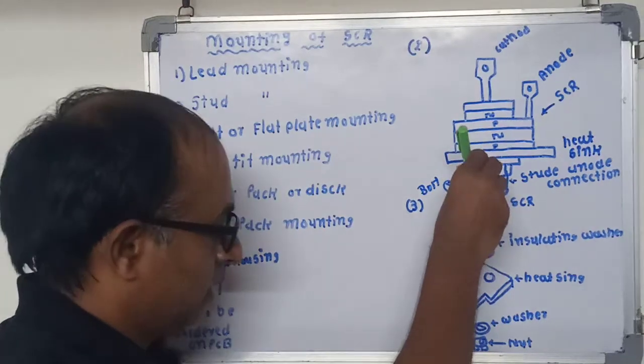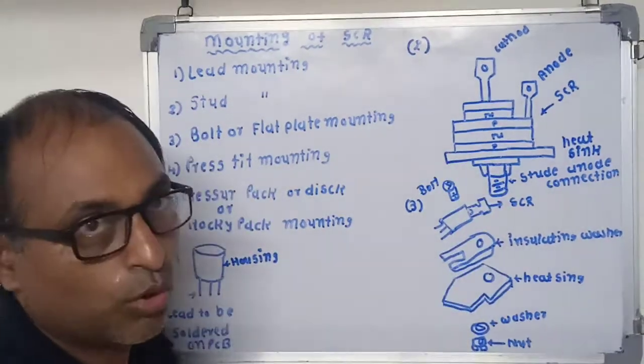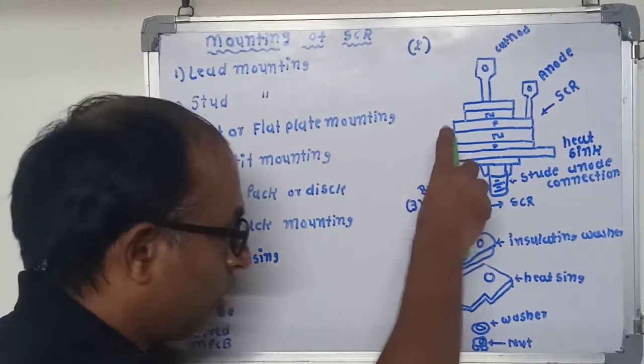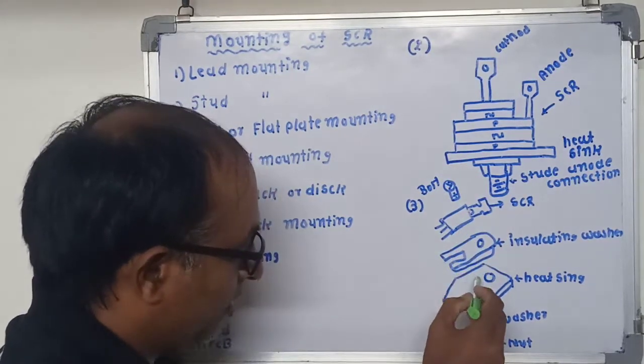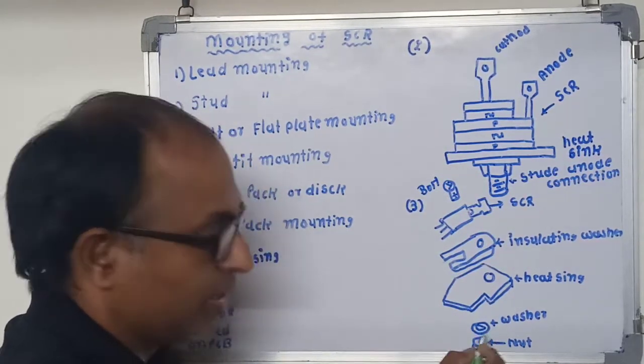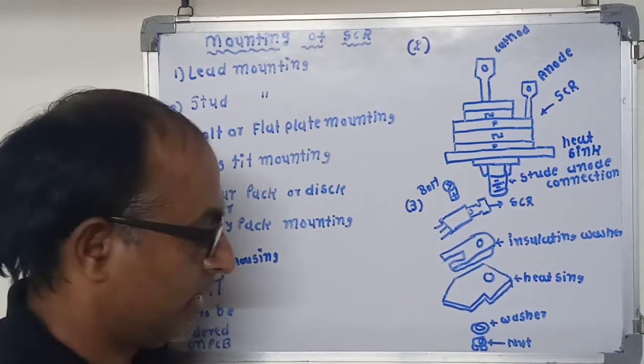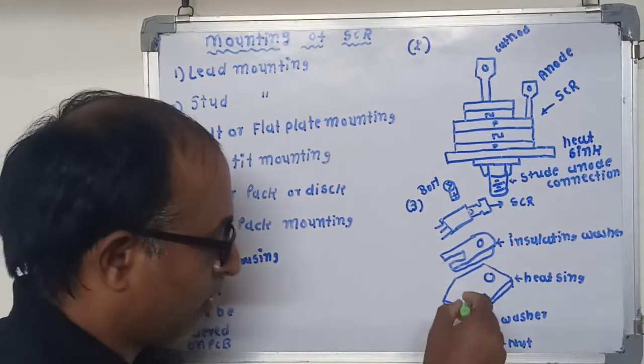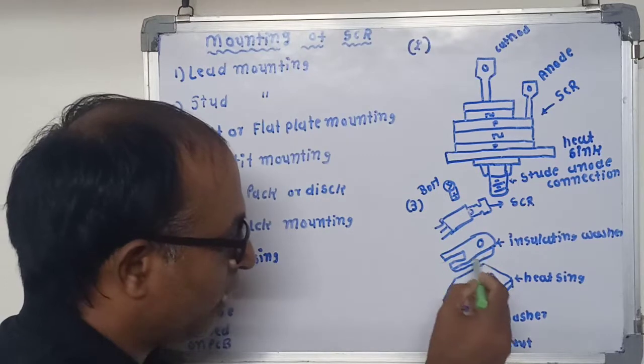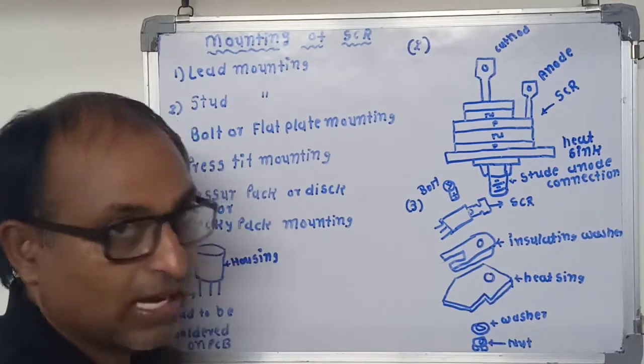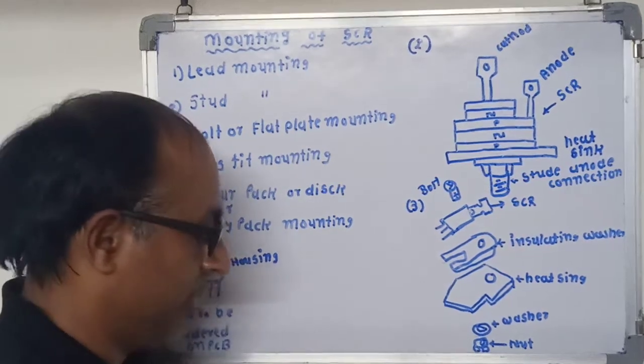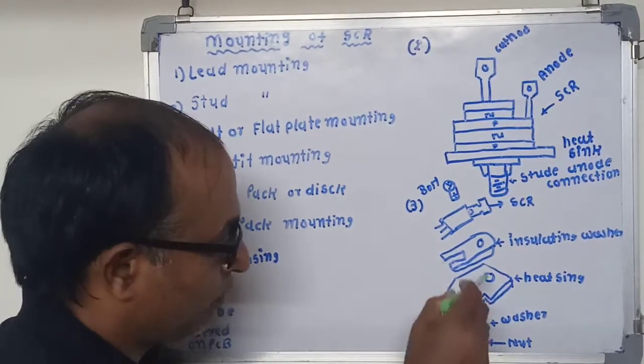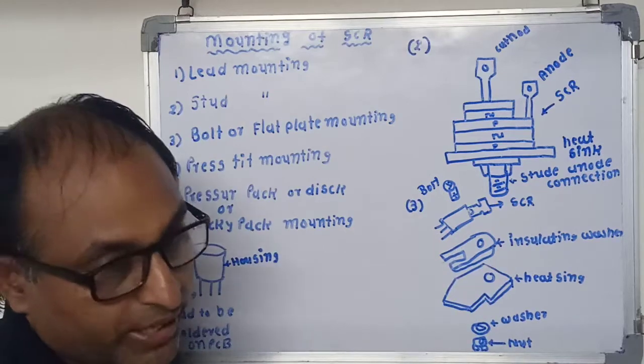Bolts are placed through these holes in order to attach SCR and heat sink with nuts. In case the SCR is to be insulated from the heat sink, thin insulating layer of mica or PTFE washer is used between them. It is used for small and medium ratings.